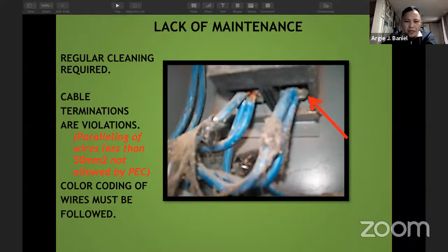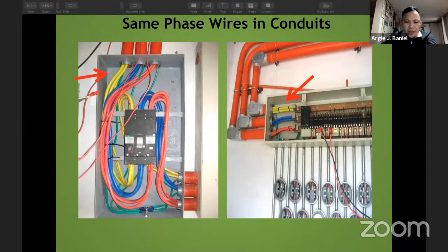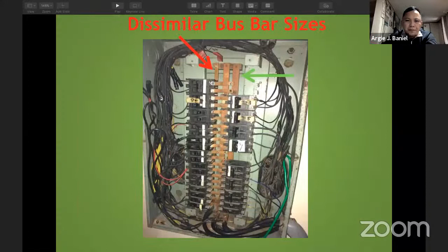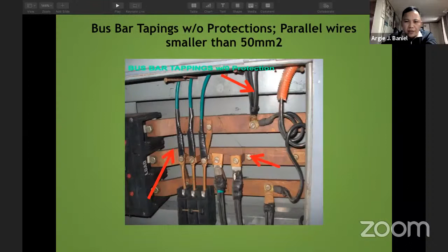Same phase wires in a conduit. That is very dangerous, so safety is lost. Because currents or eddy currents develop there, and the pipes heat up, especially if iron pipe or GI pipe was used. Dissimilar bus bar sizes. Okay, so the bus bar sizes are different. Bus bar tapping without protection. Parallel wire smaller than 50 square millimeters.